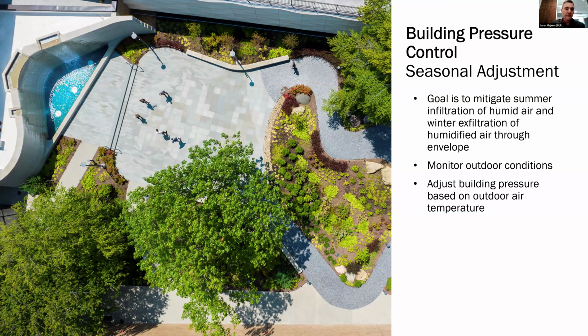So, building pressure control with seasonal adjustment. Many of you, depending on the climate you're in, may have sequences that pressurize your building and make sure that it remains pressurized, especially during the summer months. And in general, that is great. Having that pressurization helps mitigate infiltration. But for a highly humidified building like a museum, you have to be a little bit careful with that, especially in the winter months, because your indoor dew point could exceed the outdoor temperature, and that pressurization can drive moisture into the envelope. And depending on the makeup of the wall or the roof, you can be forcing moisture to the backside of the vapor barrier.